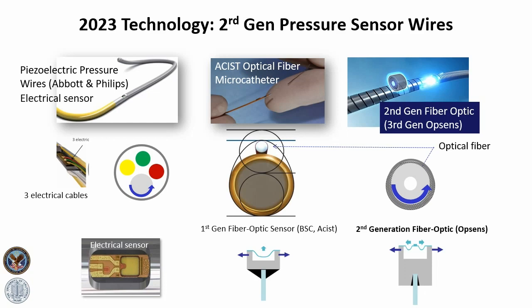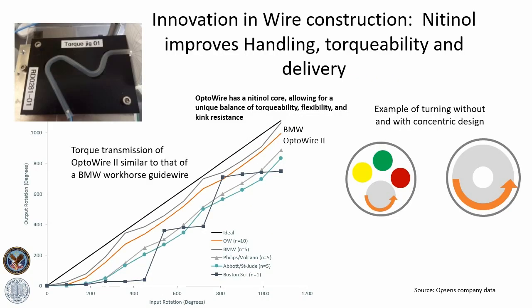It's just not necessary as much anymore because your wires on the right, the optical fiber wires, the nitinol wires, are very good handling wires. Signal stability is better, same thing. And at the bottom, the sensor generations are shown across, and you saw the little diagram of how the diaphragms work. The technical aspects of these optical sensors are much better and much more stable than piezo wires.